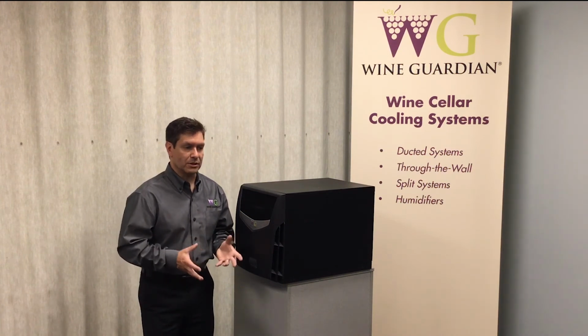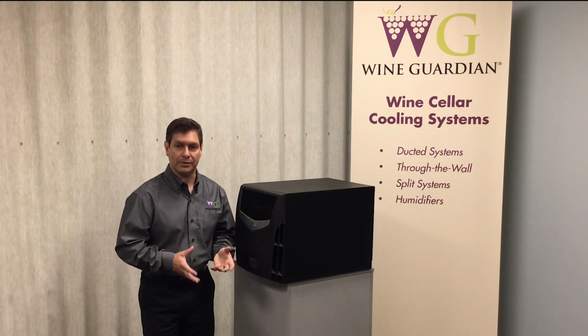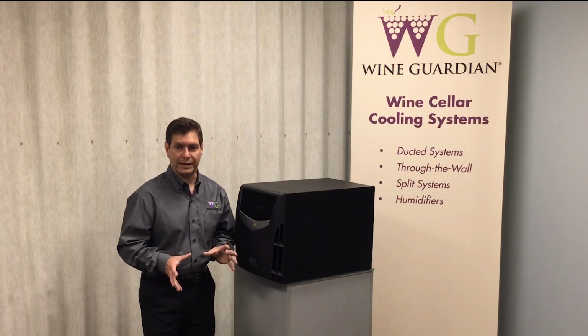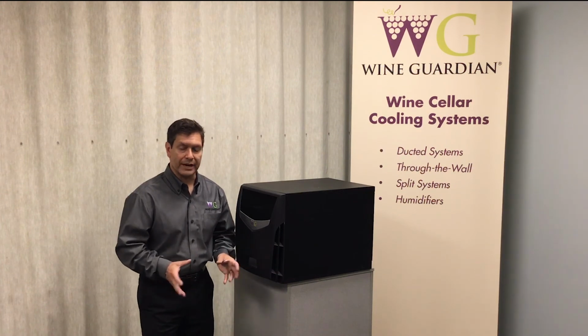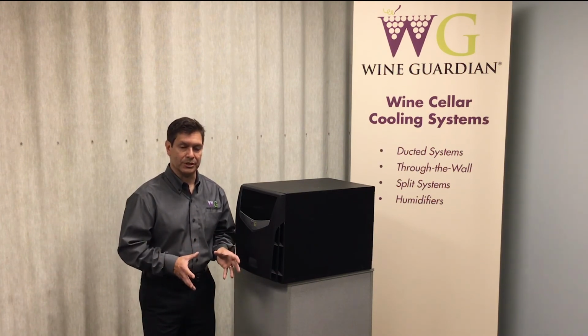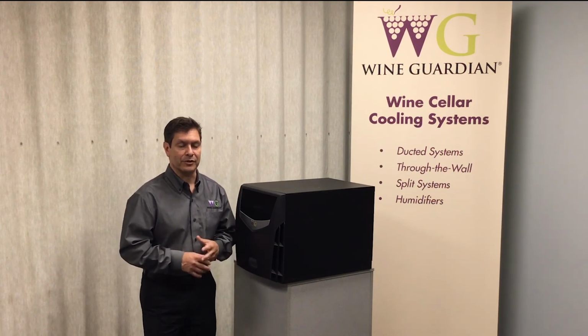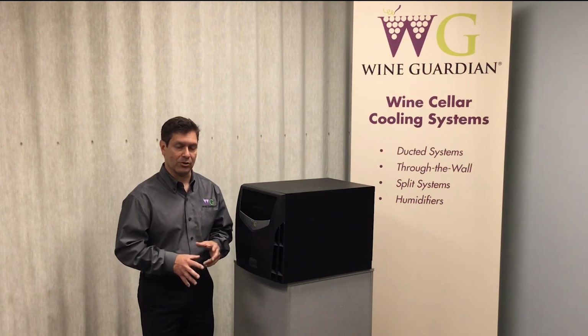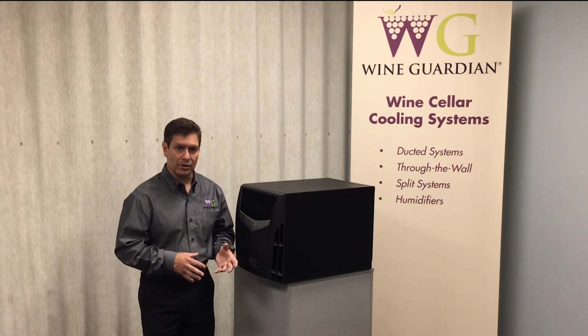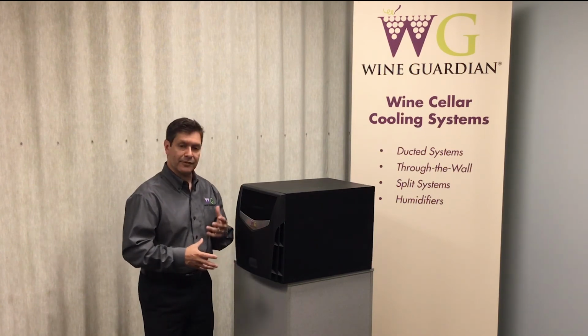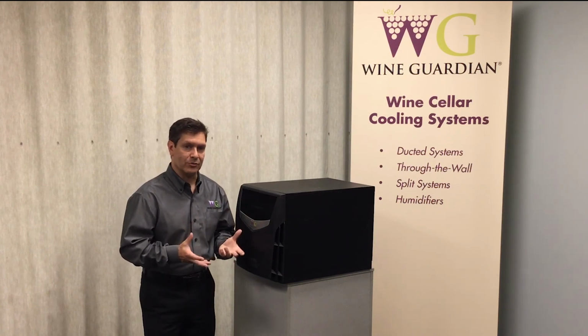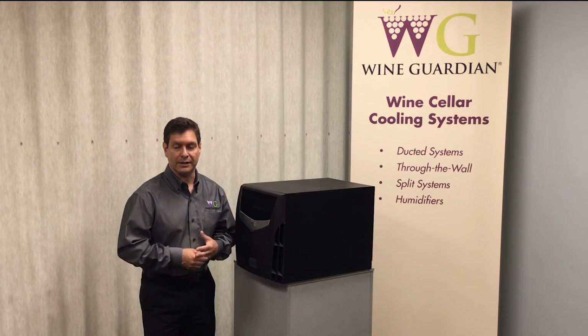It's always a good safety measure to connect up a drain to the unit and take it away to an open floor drain or condensate pump as a permanent solution. That's always a good idea, but if you don't have the capabilities to do that, or it's very difficult for your room or application, then you may want to see if you'll have condensate removal issues up front, and then take care of it after that.